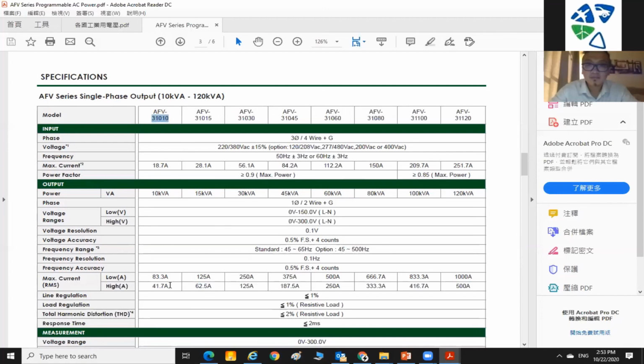It depends on what kind of testing you are doing. Sometimes the customer says they want to do locked rotor testing, which needs continuous startup current - that's different, so you may have to choose the 30 kVA unit or higher. But if you just want no-load testing, just to power up the motor, we can help with that. You don't have to choose such a big unit, which saves you money, and we can choose a smaller one and still help you overcome the inrush current.